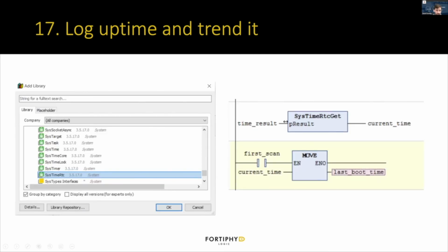Using CODESYS, one way to do this is importing the SysTimeRtc, or real-time clock, library. You can read that with the function block SysTimeRtcGet. Then you can track when the PLC rebooted by having a first scan bit where you read the current time and store it in a last boot time variable that you display on the HMI to help log when the PLC rebooted.